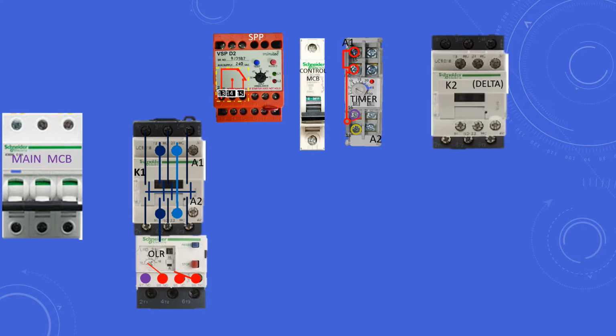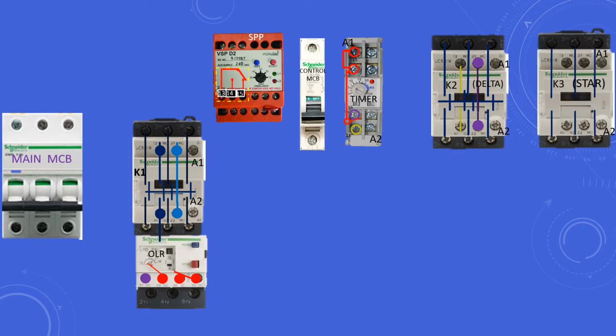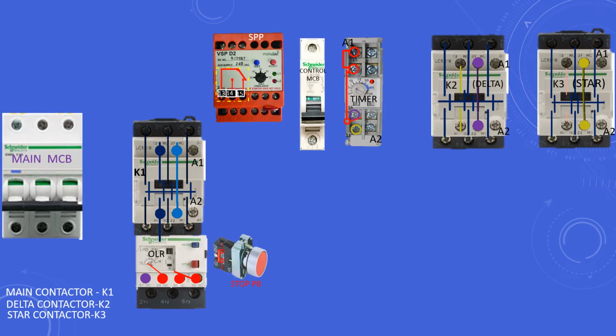This is the 3-phase contactor K2 of suitable rating. The contactor connects the motor winding with delta connection. This is 3-phase contactor K3 of suitable rating. The contactor connects the motor winding with star connection. This is stop push button. This is start push button. Now please watch the wire connection of the starter. Neutral wires are connected at A2 of all voltage coils of all instruments.